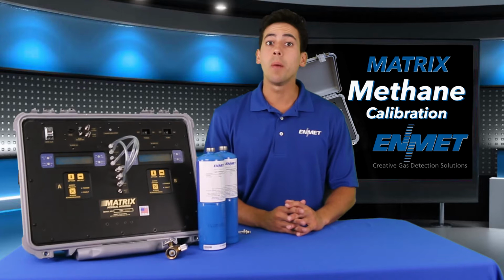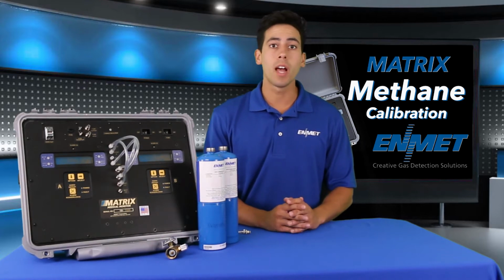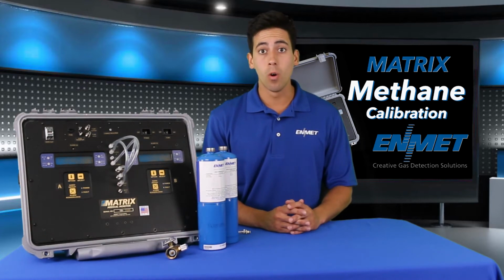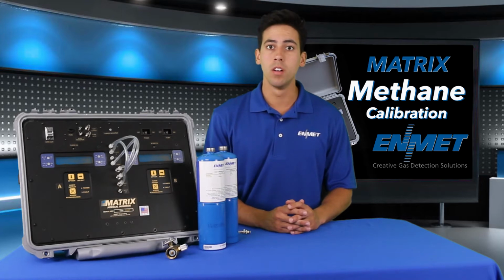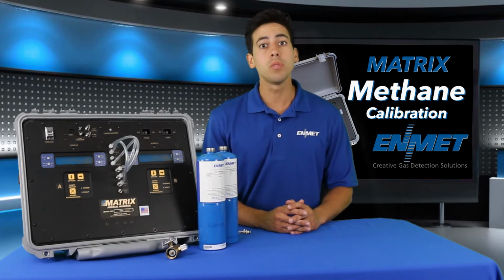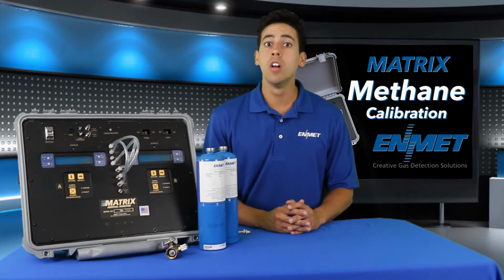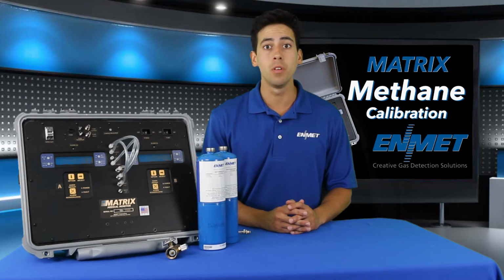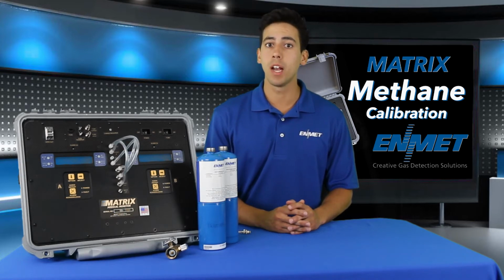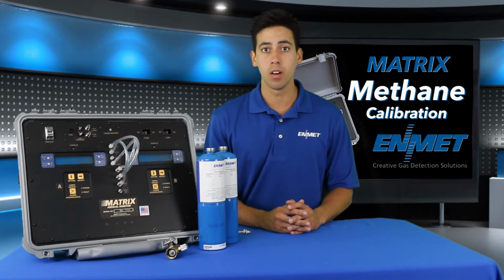In this video, I'll be walking through the matrix calibration for the methane or CH4 sensor. Please note, if your matrix is configured with the CO2% by volume channel, this calibration procedure also applies, and this procedure should be followed using the proper CO2% by volume calibration gas and adapter. If you need help with setting up your matrix for calibration, please see our matrix setup video.